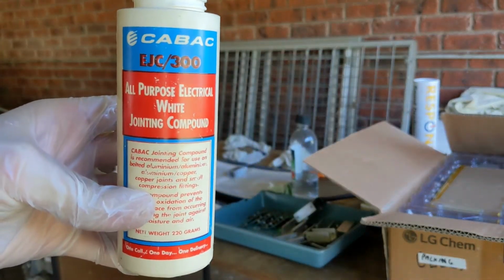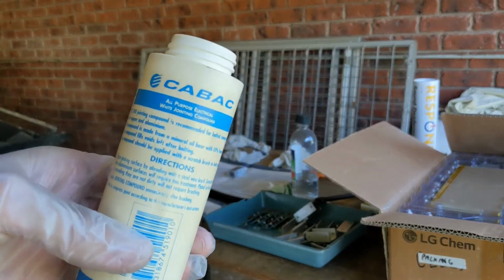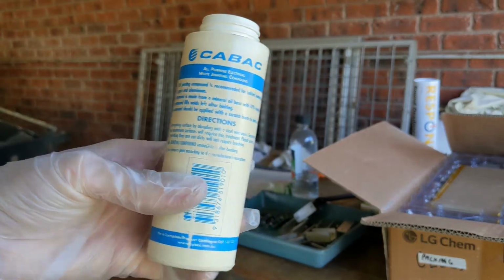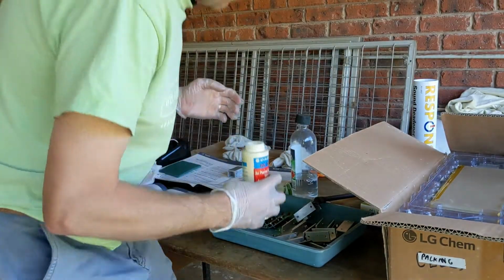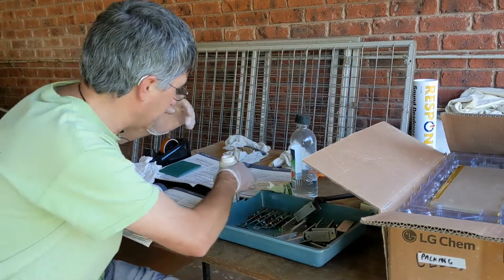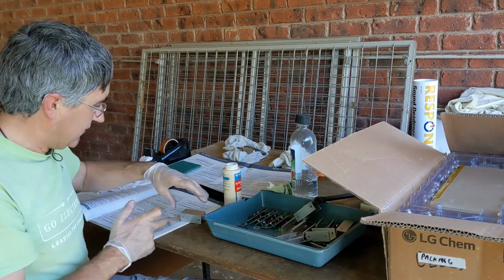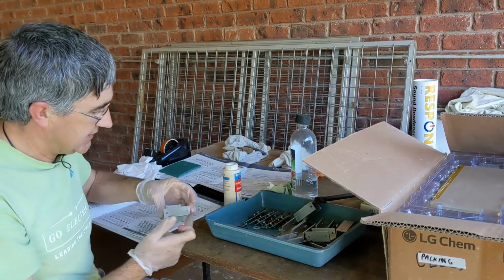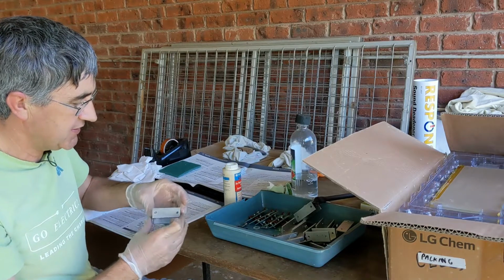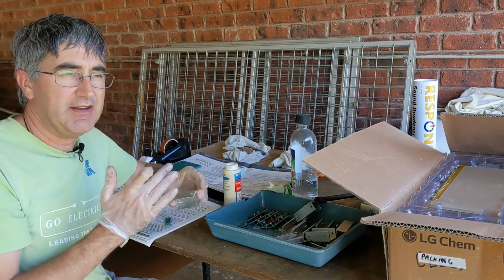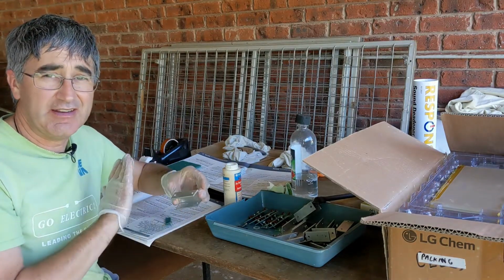That's this particular one. It's designed to stop the aluminium corroding. With aluminium, it gets a surface layer of aluminium oxide when it reacts with the air, and that isn't good at conducting electricity, so you need to clean that off.